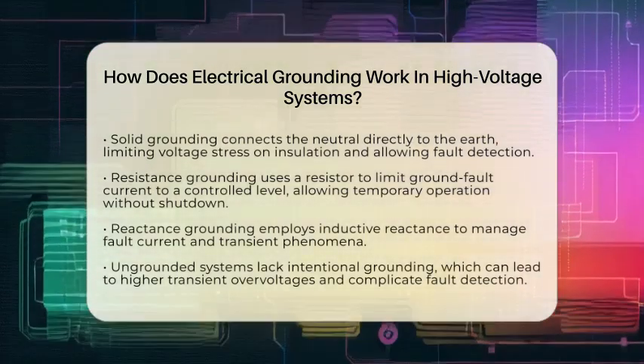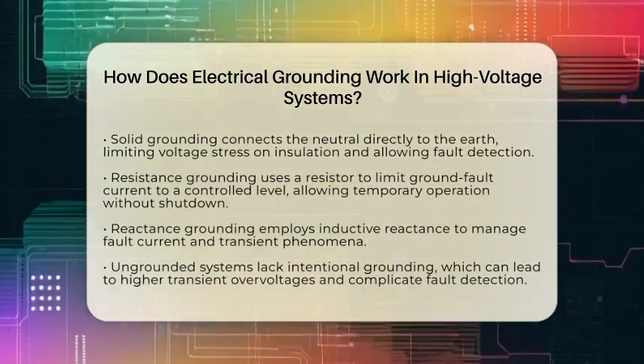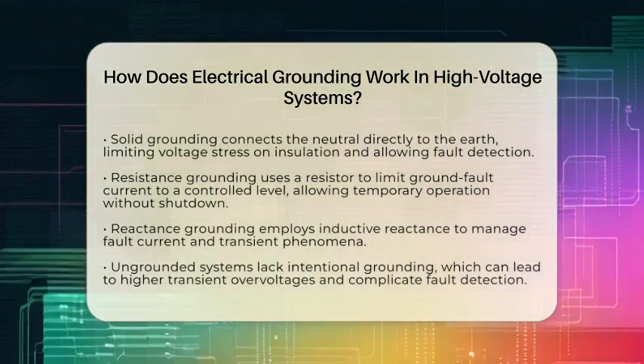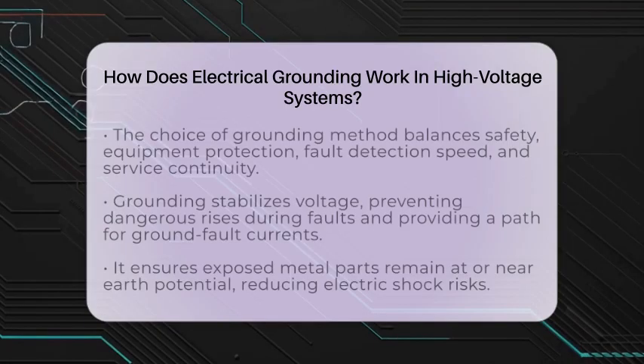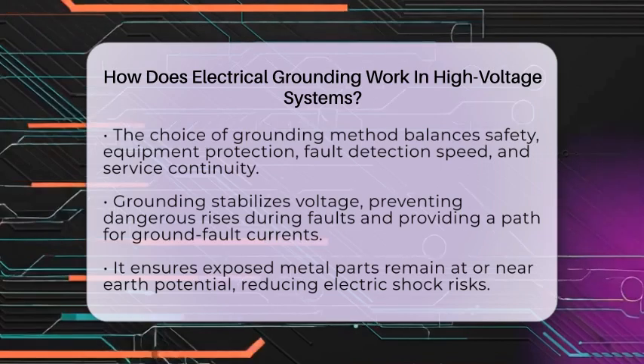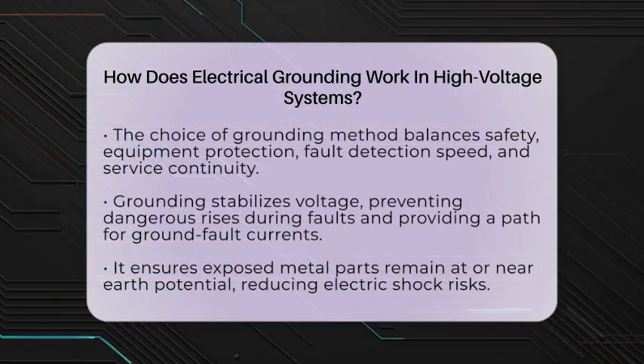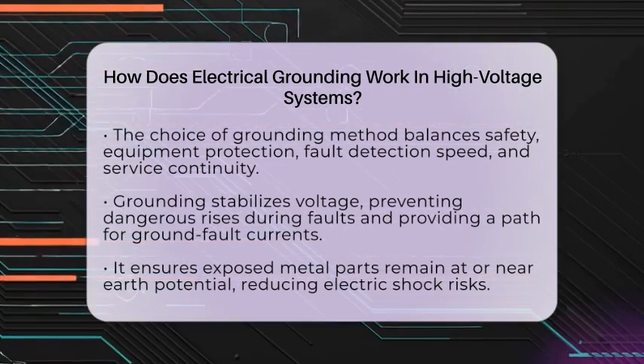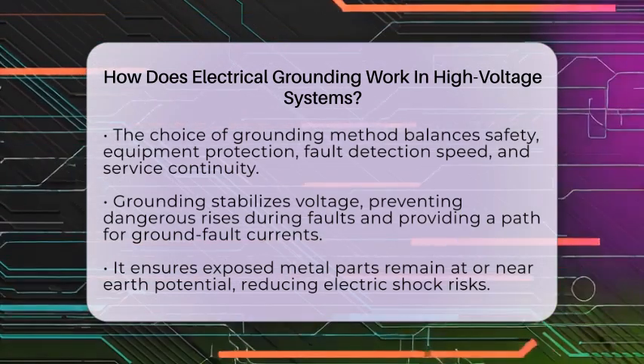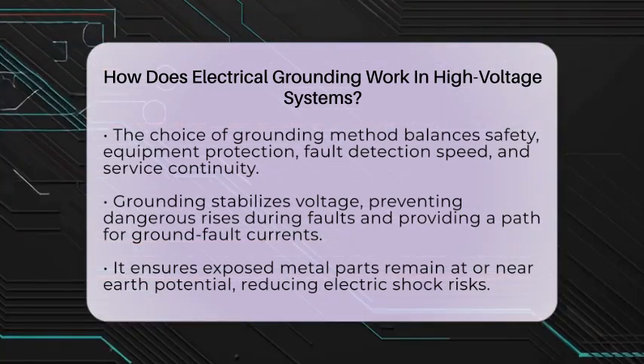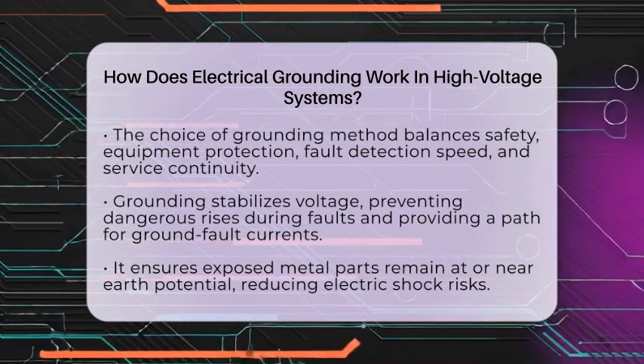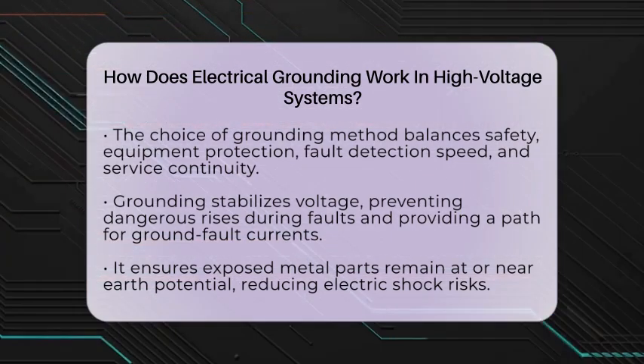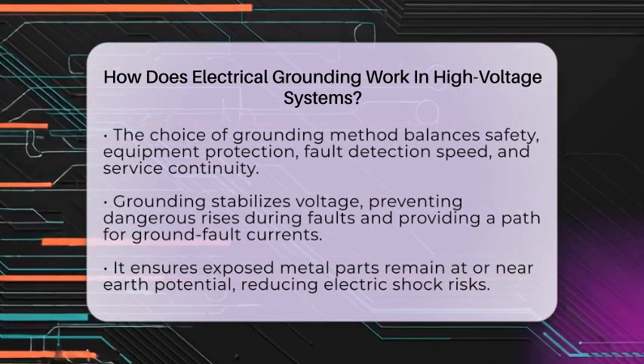Lastly, there are ungrounded systems. In these systems, there is no intentional grounding, but natural capacitance to the earth may exist. This can lead to higher transient overvoltages and make it harder to detect ground faults. The choice of grounding method depends on balancing safety, equipment protection, fault detection speed, and service continuity.